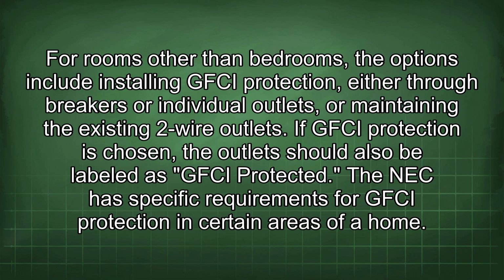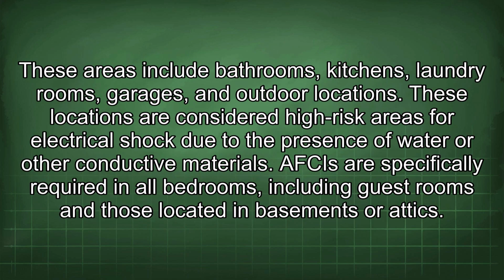For rooms other than bedrooms, the options include installing GFCI protection either through breakers or individual outlets, or maintaining the existing 2-wire outlets. If GFCI protection is chosen, the outlet should also be labeled as GFCI protected. The NEC has specific requirements for GFCI protection in certain areas of a home. These areas include bathrooms, kitchens, laundry rooms, garages, and outdoor locations. These locations are considered high-risk areas for electrical shock due to the presence of water or other conductive materials.